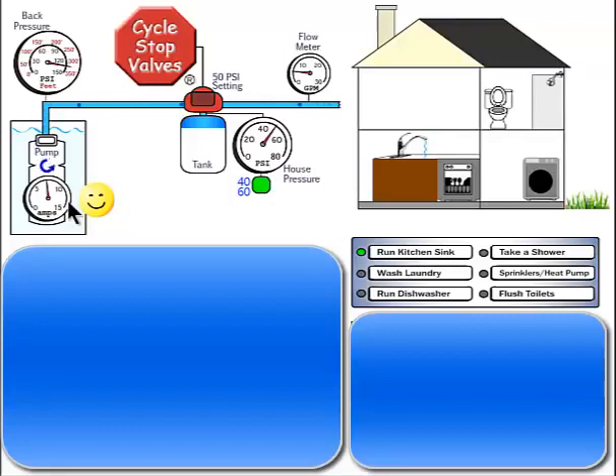Some pump brands are better than others, but some pumps, like the 2 horsepower in this animation, can drop as much as 50% in amperage when restricted. This pump will draw a maximum of 14 amps while using 25 gallons per minute and can drop to about 7 amps when restricted to very low flow like one kitchen faucet. A 14-amp motor loping along at 7 amps is using about half power. Half the amps is also half the heat, so the motor is happy and running cooler.